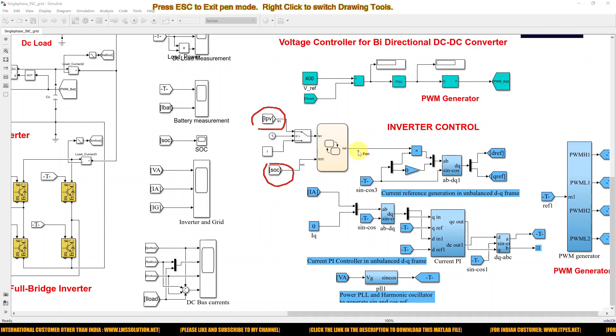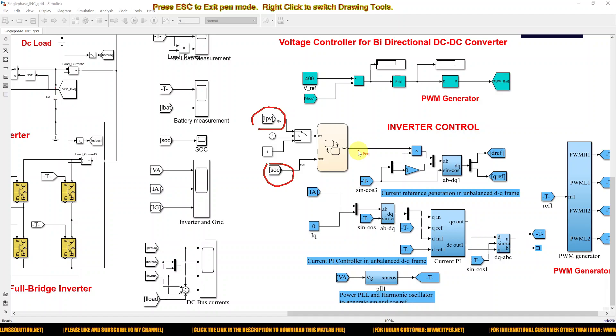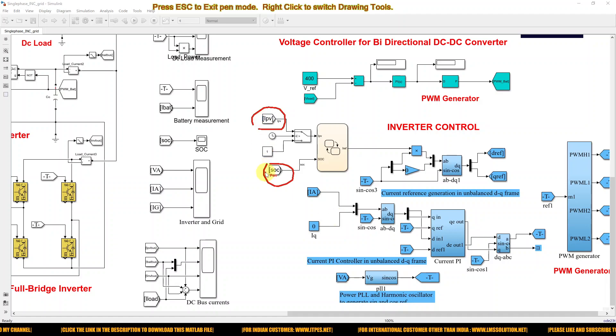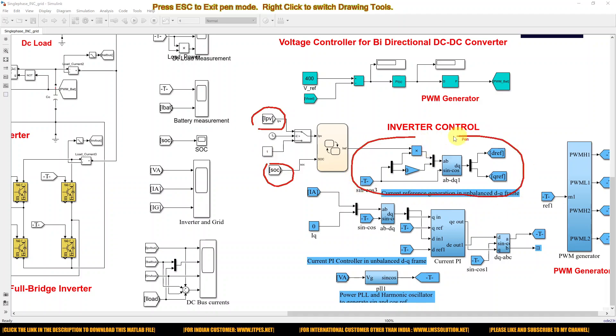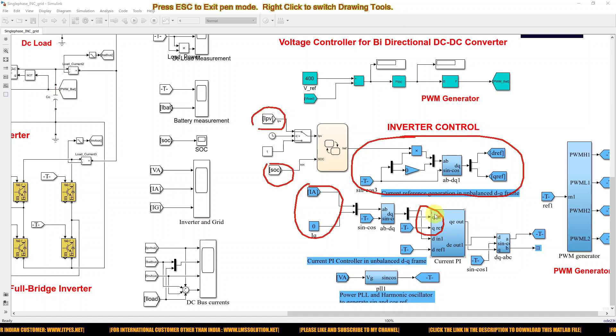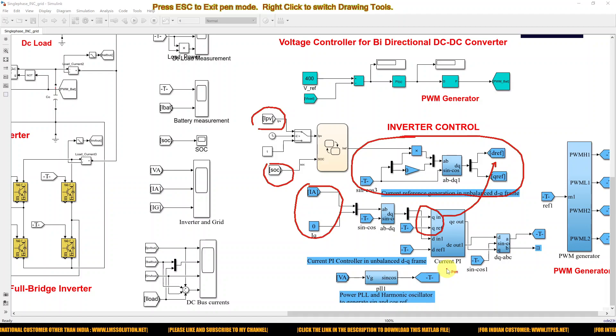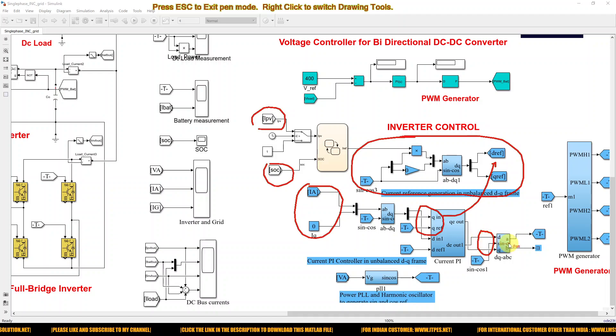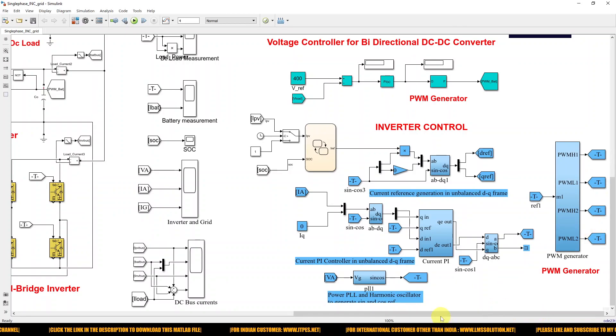Based on these two parameters — PV current and battery SOC — we decide the reference current: whether we are taking power from the grid or supplying power to the grid. This block generates the reference current in the DQ frame. The actual current measured from the inverter is also converted into DQ, then compared with the reference and processed via a PI current controller, which generates the control signal in DQ form. This is converted into ABC quantities, and only the A-phase quantity is used to generate the gating pulses for the inverter.